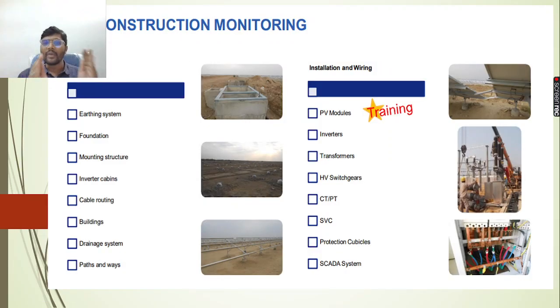Then in construction management, when you are going for civil work, you need to look at whether all the civil structures are installed as per the plan that we designed. First and foremost, you need to check whether the earthing system is installed. Then whether the mounting structures have arrived and been installed as per the drawing. Then we need to look after the inverter cabins and inverter rooms. Then we need to make sure the cable has been routed as per the design drawing, and the buildings for the inverters have been constructed. Then we need to keep track of the drainage systems also, because you might be planning some solar panel installations on the ground, or on rooftops. But drainage management is very important. Make sure the rainfall falling over the site is collected at different locations.